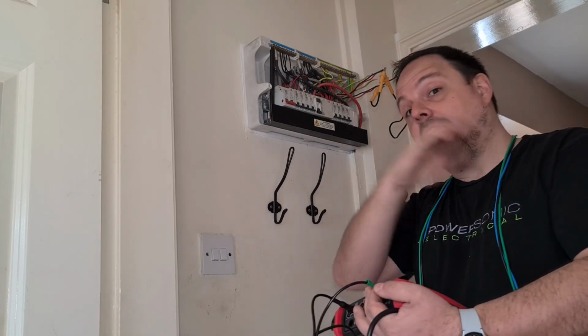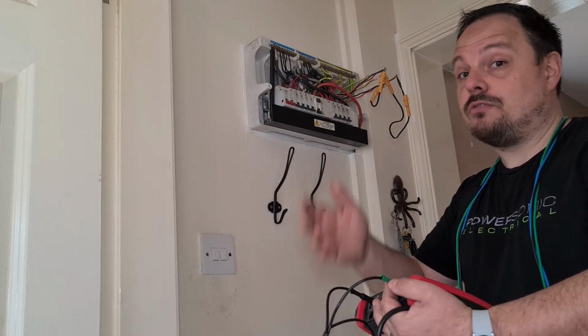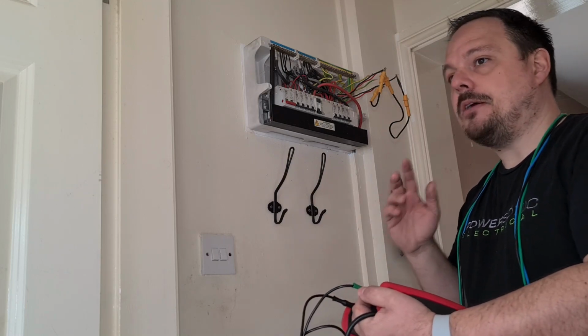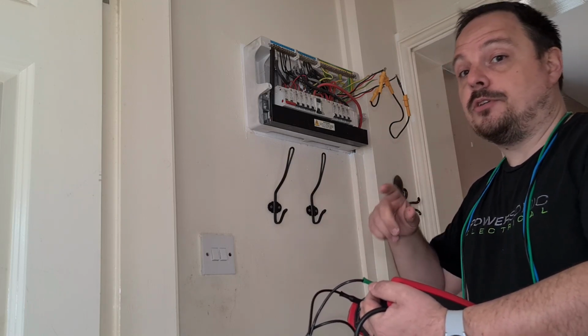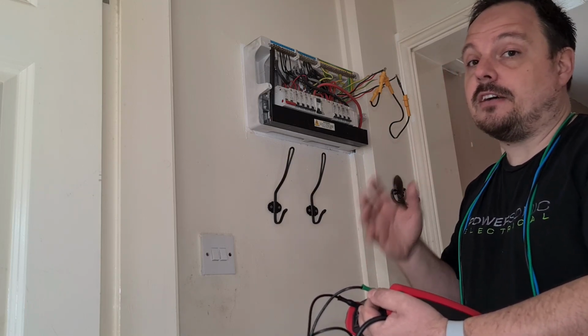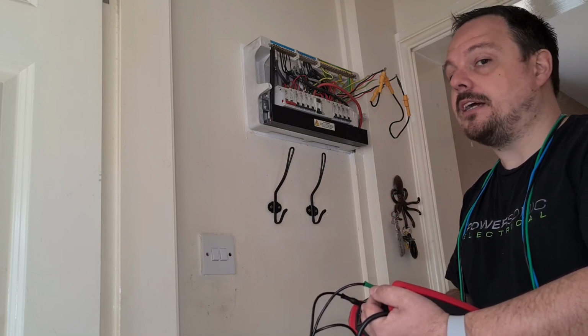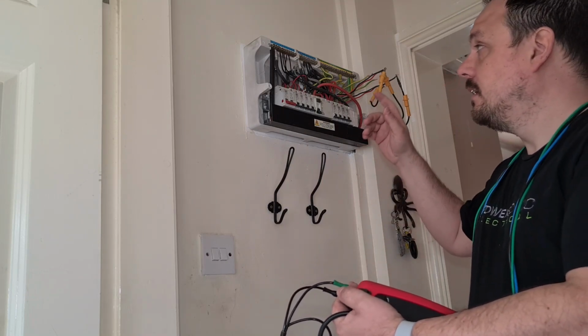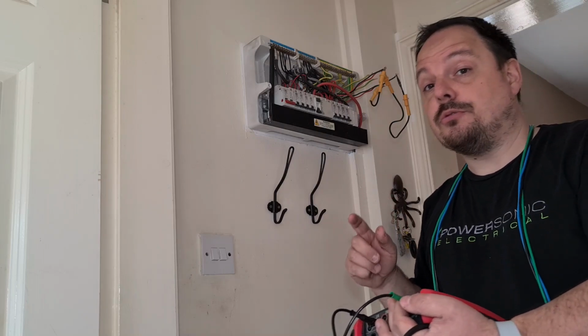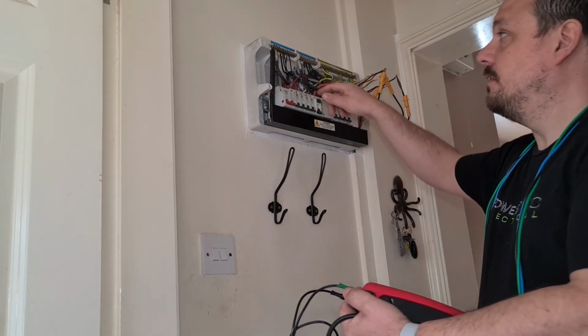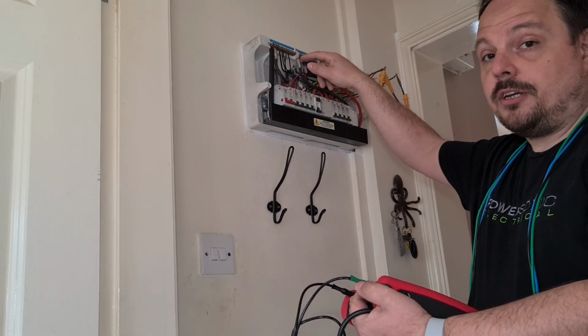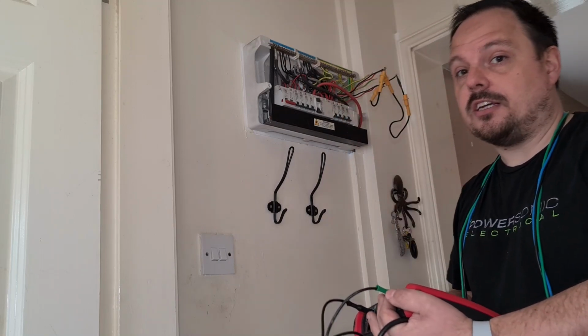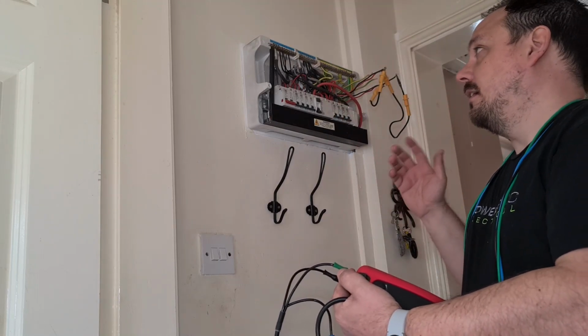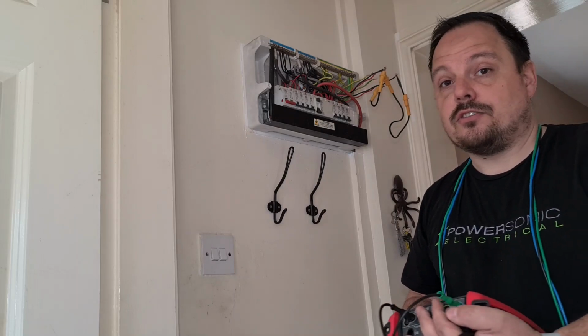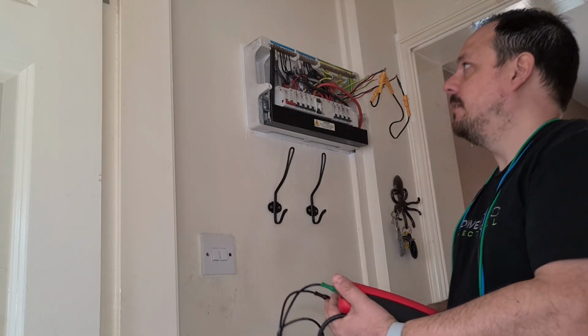And then basically you find the end point of that radial circuit, so that's a radial, not a ring, and you go and take a measurement between the line and the CPC, and that's the value of your big R1 plus big R2. And then again, you can repeat that process with the neutral as well. So you can cross over with the line and the neutral at the consumer unit, and then go off to the same point of that circuit and take another measurement. And that's just a way of verifying that all your circuit conductors have continuity from end to end.